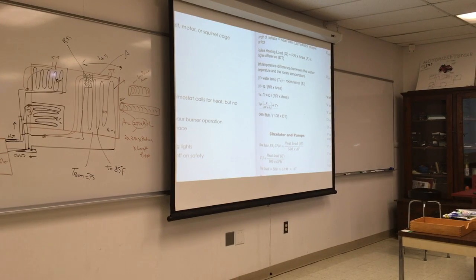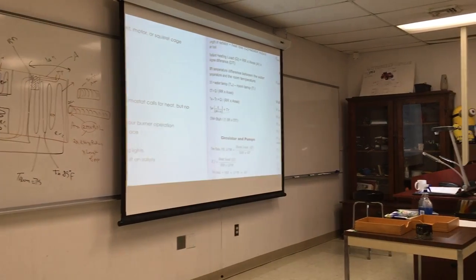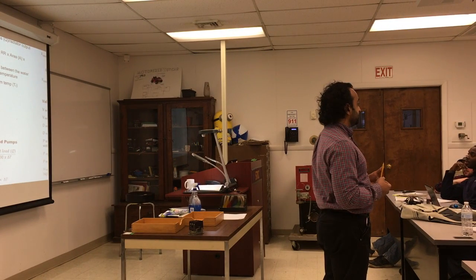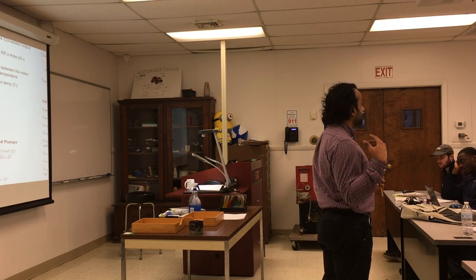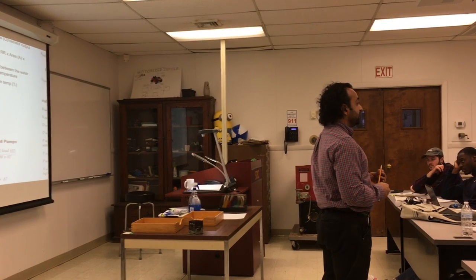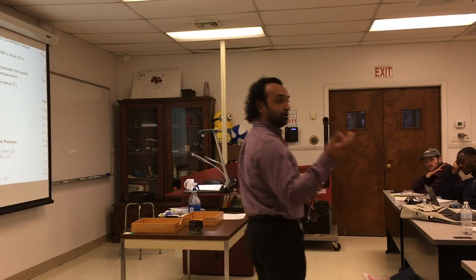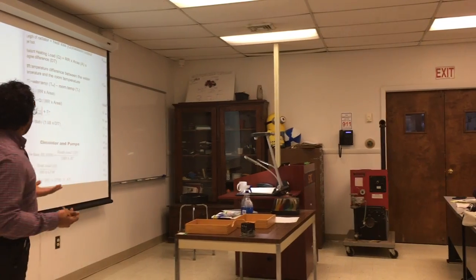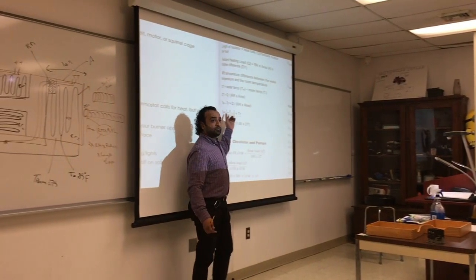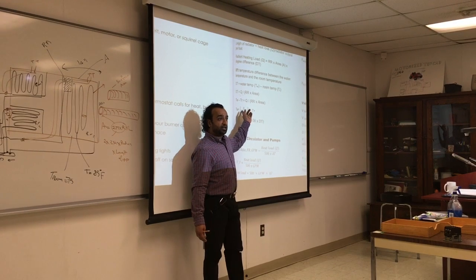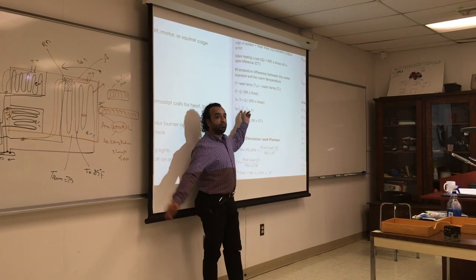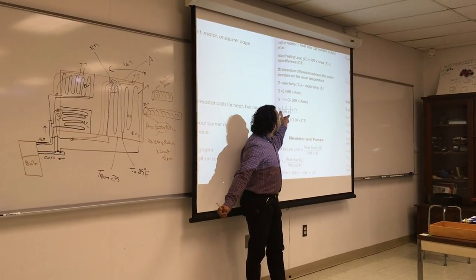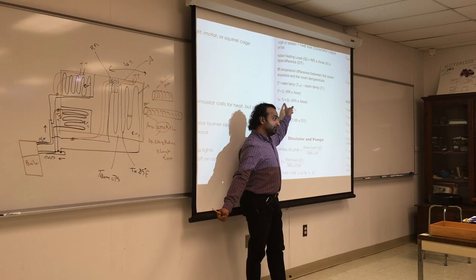Let's say I had a room that was emitting 10,000 BTU. The owner decided that this is too much, he put some insulation in, now the room is too hot. So what adjustment do I make to have the system run without a lot of cycling? He can turn it on and off all the time, but that's not something you want, right? So what water temperature decrease is required for me to achieve that heat loss? I can go from 85 to 75 to 70 or what have you. I'm going to find the water temperature required if I want to change the heat loss.